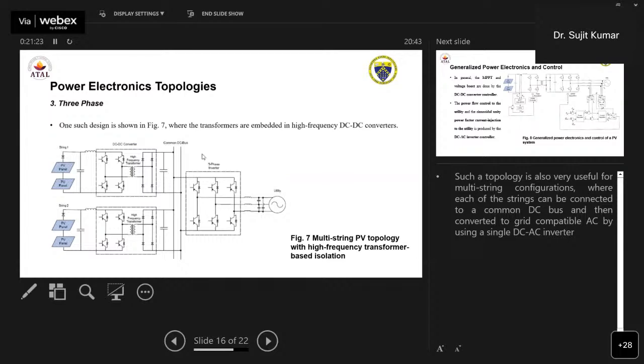One such design is shown here, where we are using transformers embedded in the high frequency DC-DC converters. You can see here, suppose this is my string 1. This is my DC converter with the high frequency transformer connected to the common DC bus. You can see string 2, string 1, like this parallel strings you can connect to a common DC bus. This topology is very useful for multi-string configurations, because each of the strings can be connected to a common DC bus, and then we can convert to grid compatible AC by using a single DC to AC inverter. So we are using the high frequency embedded DC-DC converters, with the help of high frequency transformers, in the form of galvanic isolation.